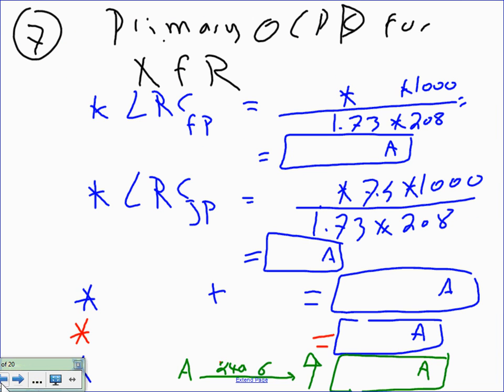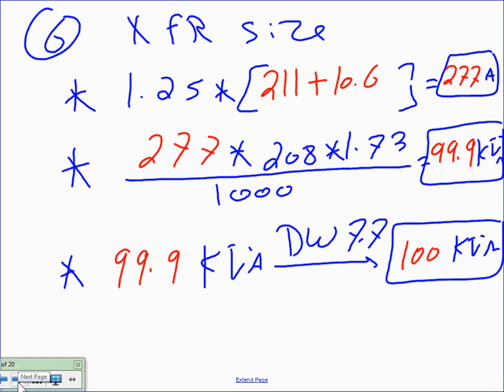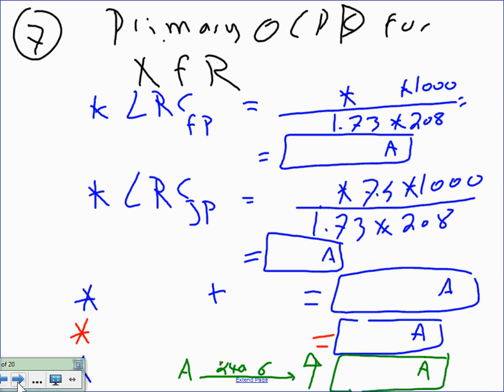Okay, so that's the size of the transformer that we decided on based on the code. And I don't write the code references, guys, because you have them on a sheet in front of you. Sure. So just to expedite the process. Okay, now the second thing, Nick, getting excited before the holiday, huh? Yes. Primary overcurrent for the transformer. We need to find the primary overcurrent, not secondary, for the transformer. We don't put secondary, we need the primary. Primary overcurrent protection device for the transformer.